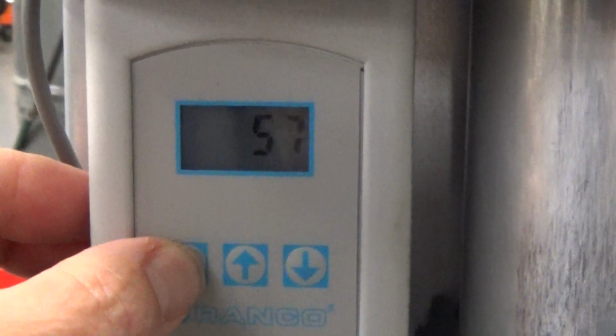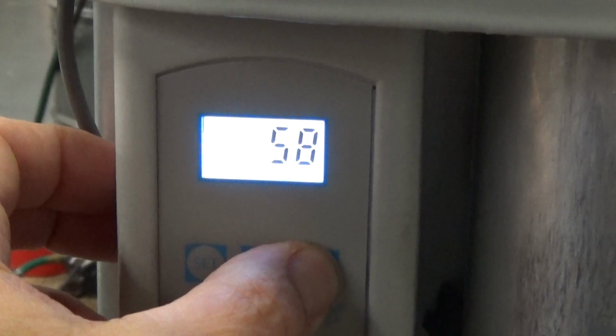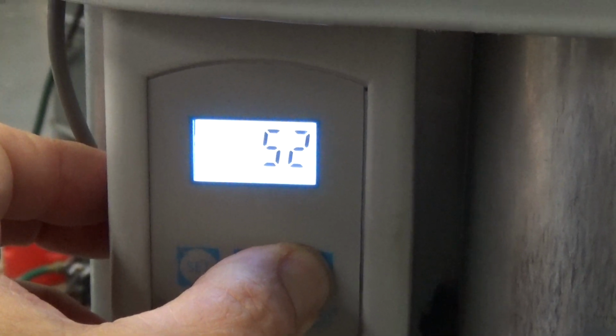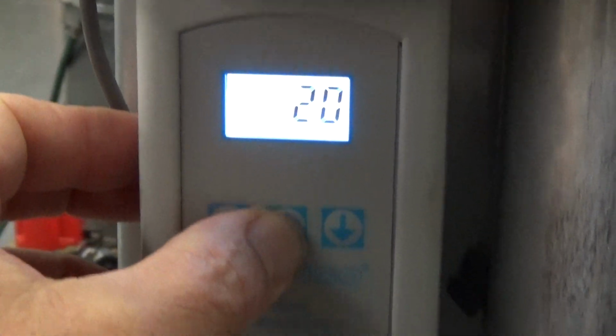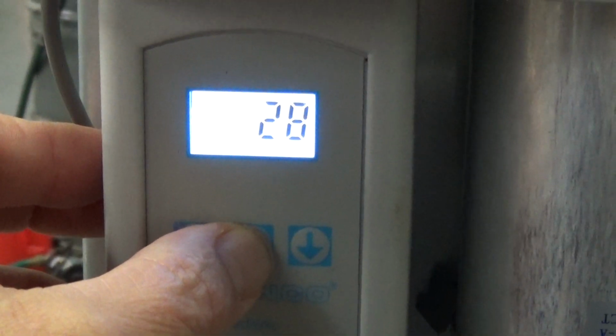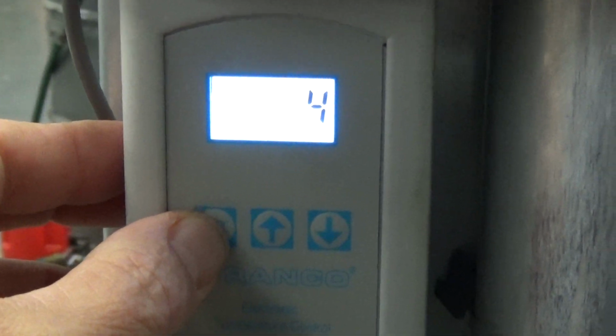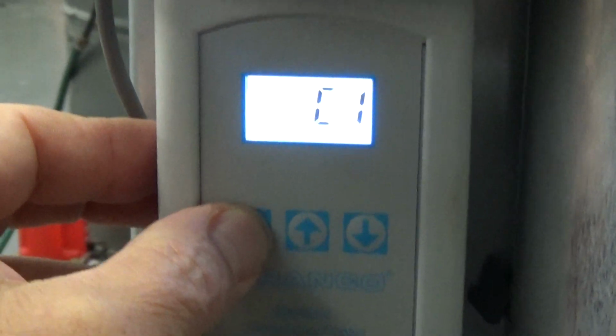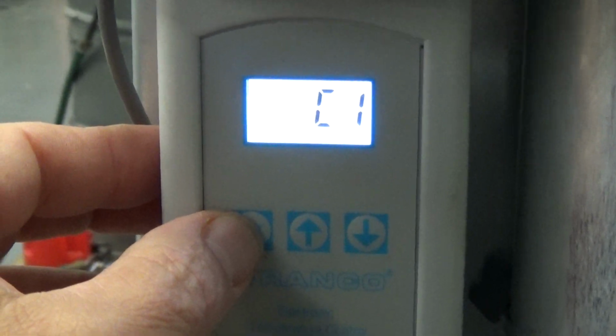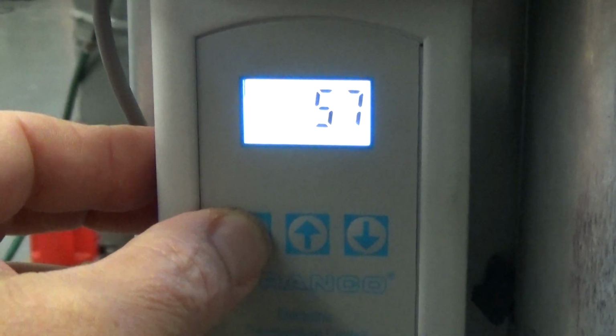So you just go up to the Ranco controller here. I have it set up at 57 right now. Just going to press set. It lights up. Get a good angle here. Set again. Fahrenheit. Set again. That's my set point. We're going to bring it down for the test run. Let's bring it down to 28. 28 glycol. Set again. 4. That's our differential. Set again. Cooling mode 1. Leave it there. Set again. It should start.